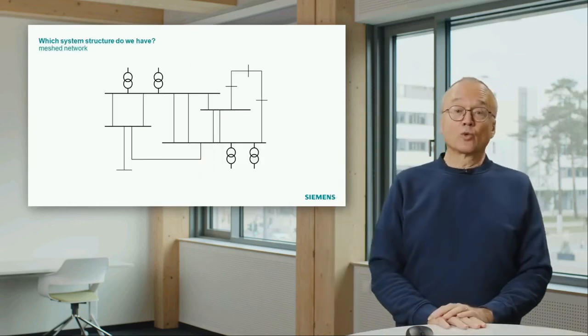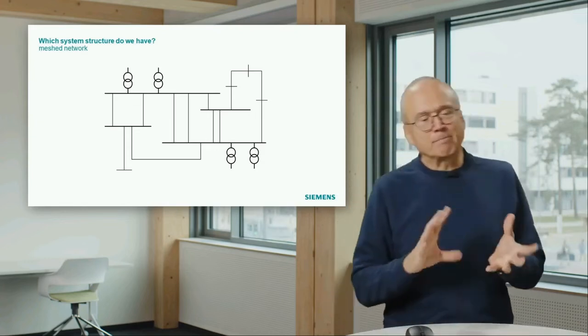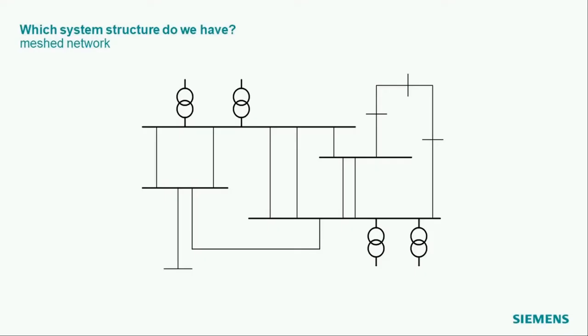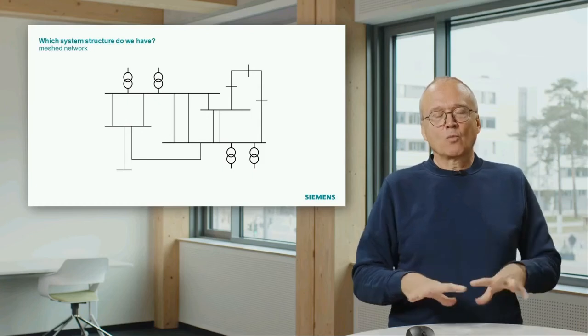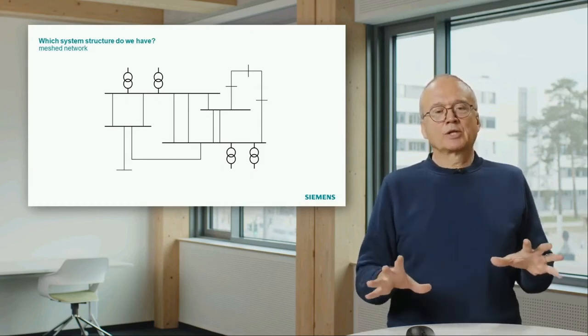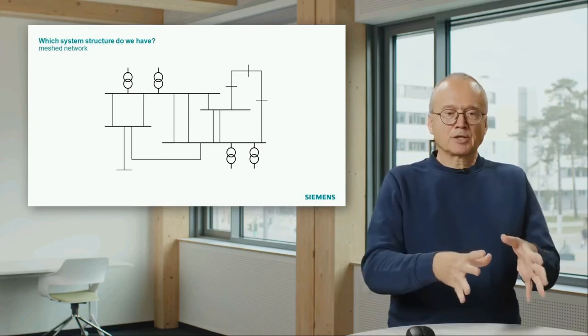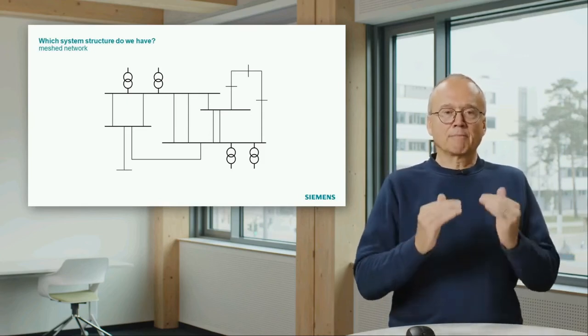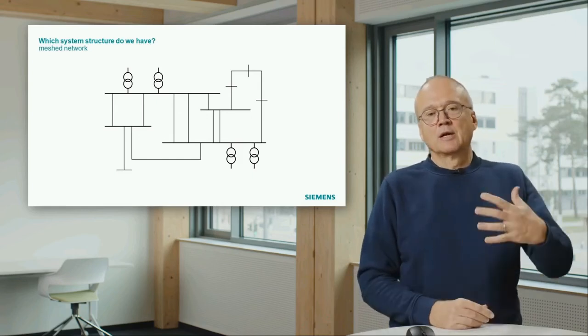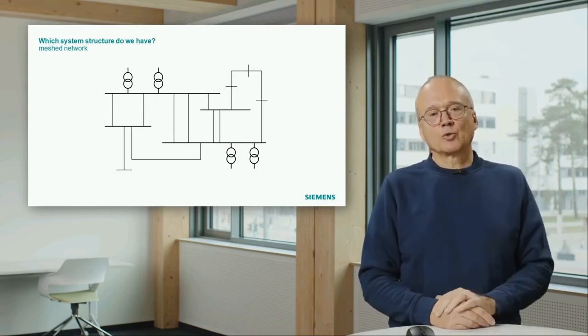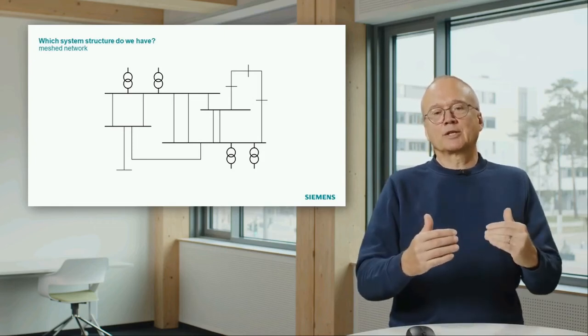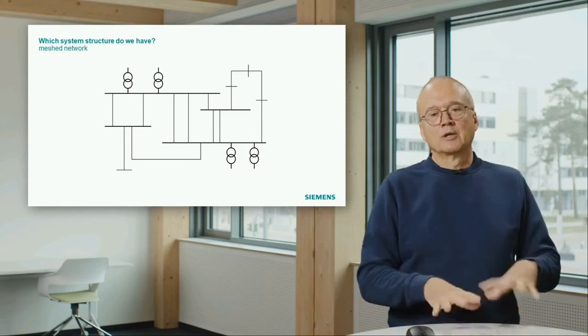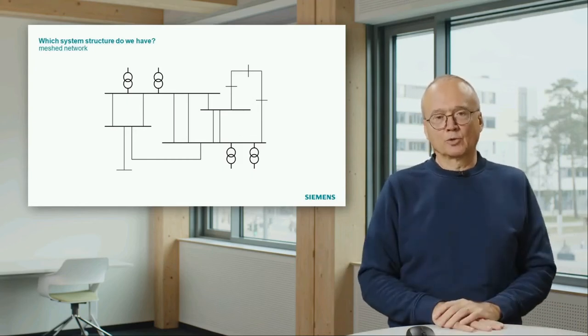We also have to look into the network structures, and they depend a bit on the voltage level. What you see here is a mesh network. That is what you typically find in transmission systems, in subtransmission systems. That means we have a mesh system which has grown somehow, which connects the power station, the generation, and the loads. The transformers you see here connect the power station to the grid, and they can also be connections from these transmission networks to subtransmission or to distribution.